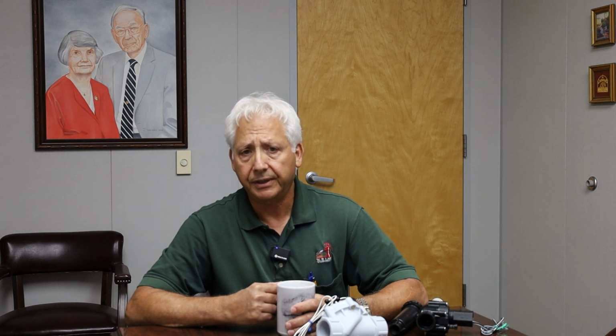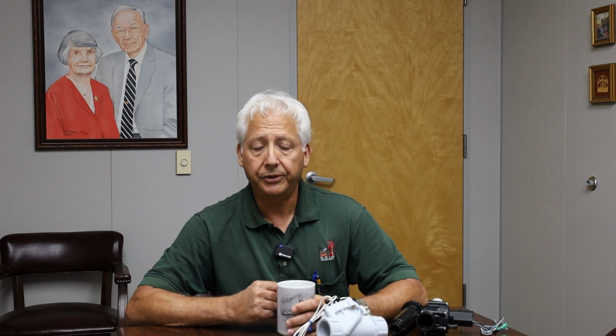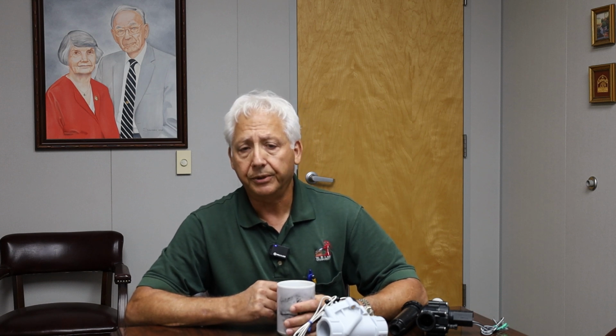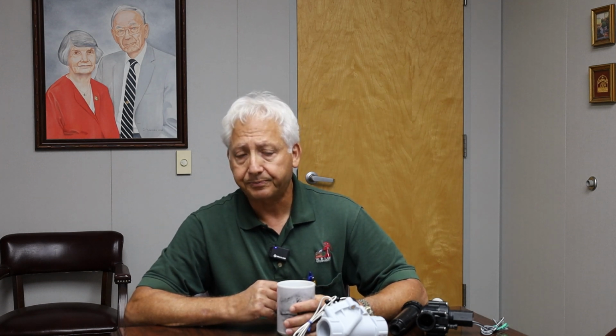Now if it's a pumping system, well, pumping system on a non-pressurized system, I should say, we'll check things like the pump start relay to make sure that's in working order. We'll check to make sure the pump circuit breaker hasn't tripped. We'll check to make sure there's no breaks in the main line, the motor isn't faulty, or that the suction line hasn't been compromised. Now from here, we'll make our way to the wiring between the controller and the valves.